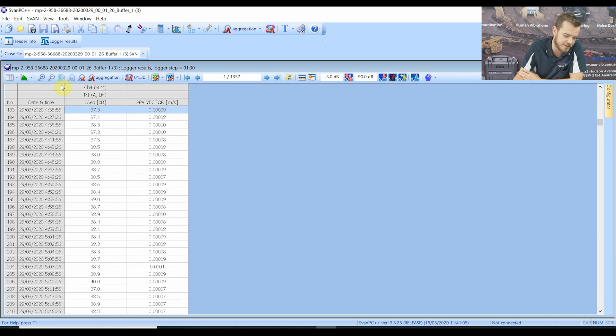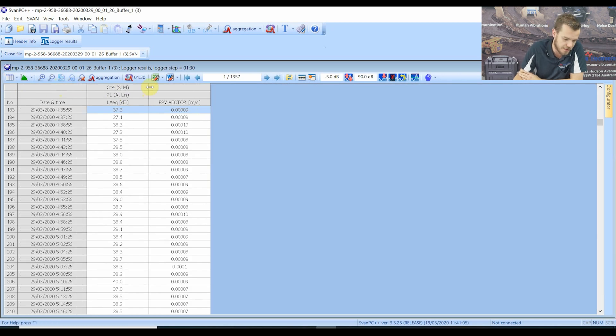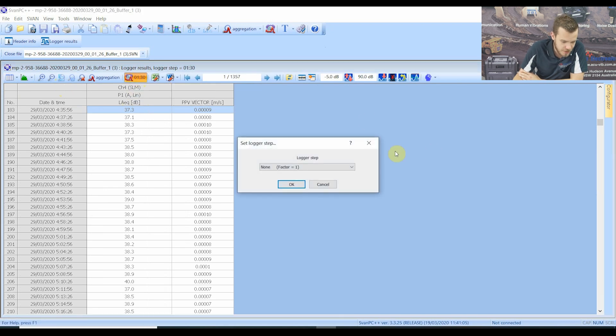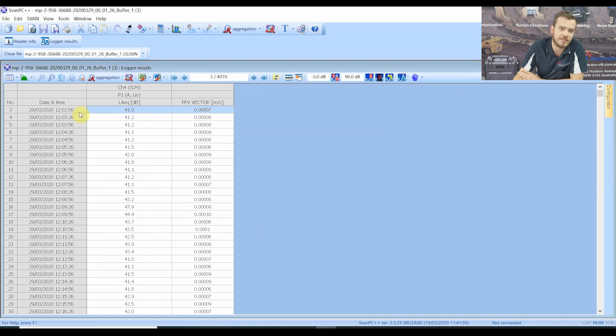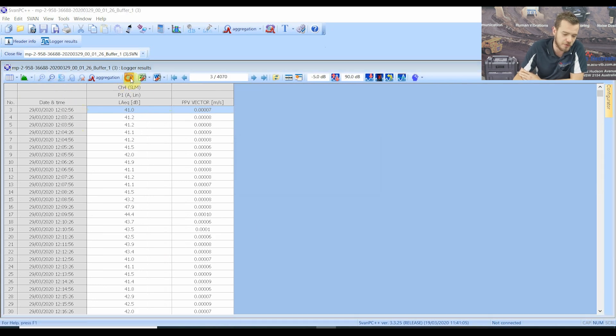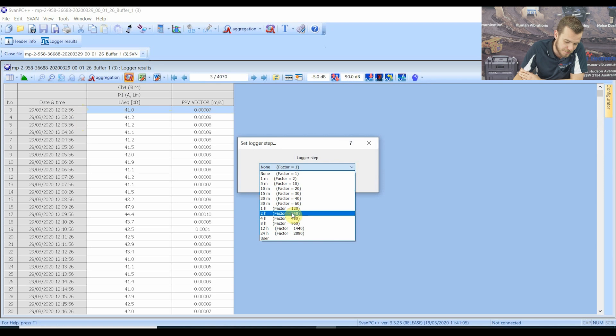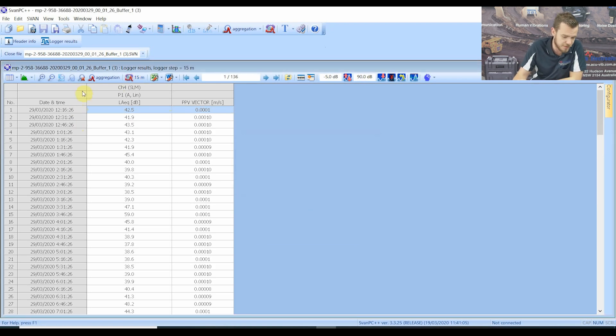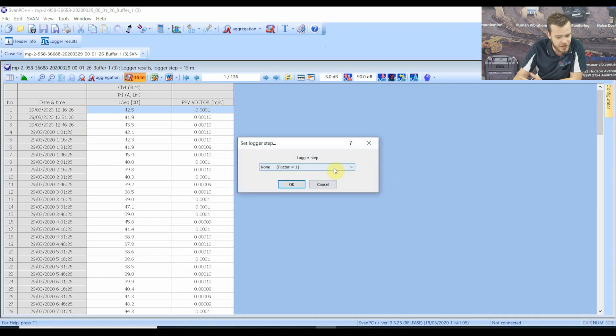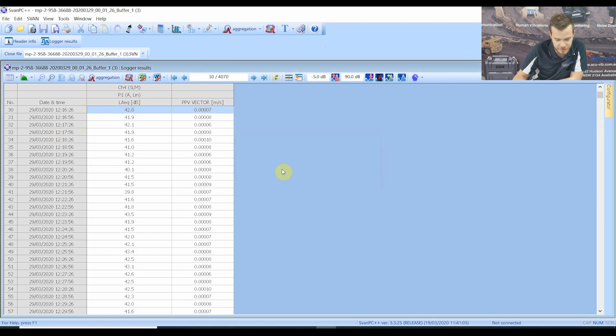Top left you have a table icon — straight away this puts everything into a table format, which is the best way to export data. Here we have a stopwatch, which is based on the logger step. If I select none, that's a 30-second logger step, which is what I set the instrument up for. You can change this to 1 minute or 15 minutes — it'll give a maximum value in that time. I'm going to leave it as per the DIN standard 30-second logger step.